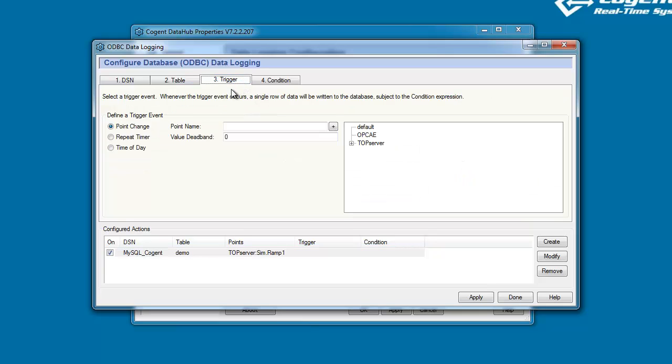If we click on Trigger, a trigger event within the Data Hub is an event which actually triggers the Data Hub to write to the database. We have three types of trigger event we can define. A point change, that is to say whenever we trigger whenever the value of a point changes.